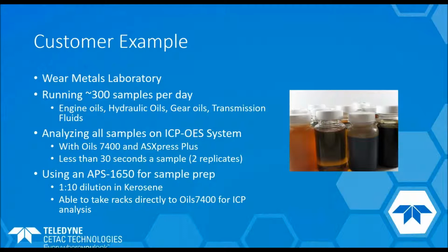And they're using an APS 1650 for sample preparation, doing a 1 to 10 dilution in kerosene, which the nice thing about that is they're able to take their diluted samples, take the whole rack from that system, and put it directly on the Oils 7400.